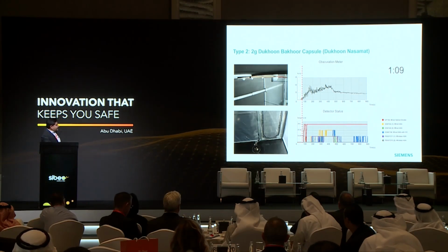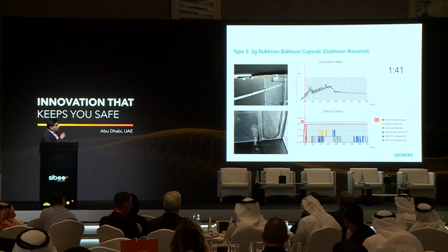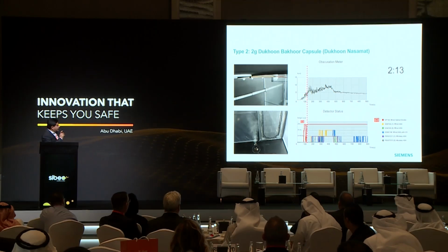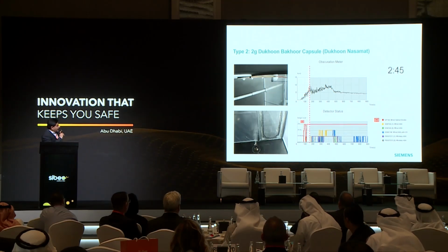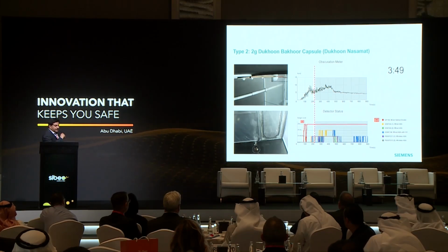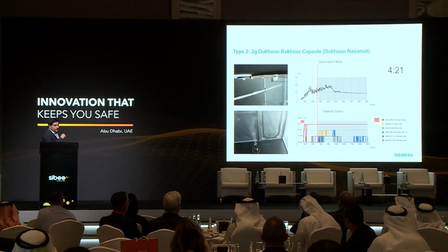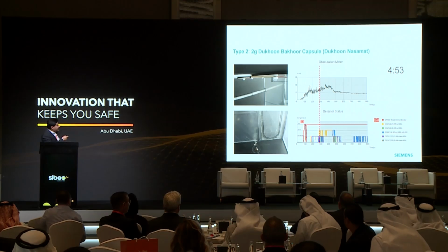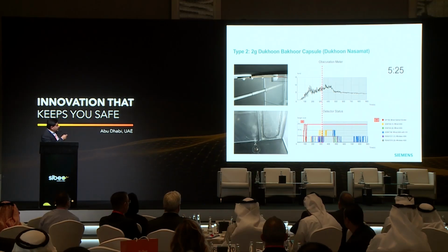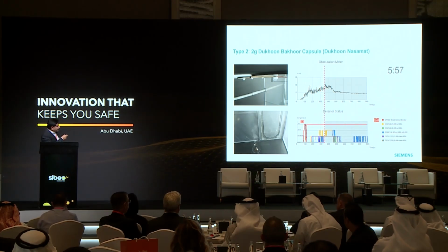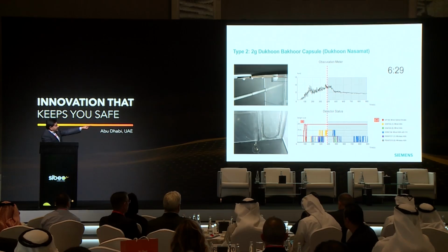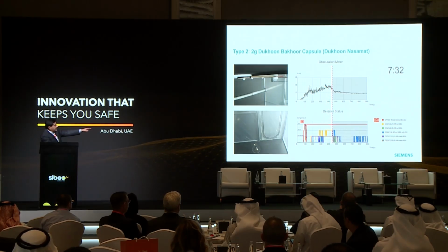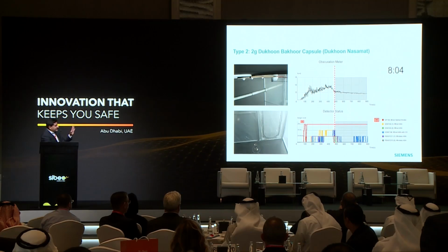So this is specifically Bakhoor content, which we used in this particular experiment. This is one of the challenges here in this part of the world, where in residences a lot of Bakhoor is being burned. And now you see the amount of Bakhoor smoke that is being given out, and the first detector, the standard optical sensor, jumped into alarm in less than 2 minutes.